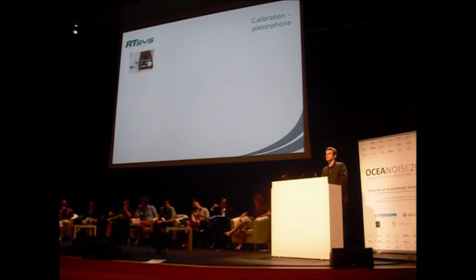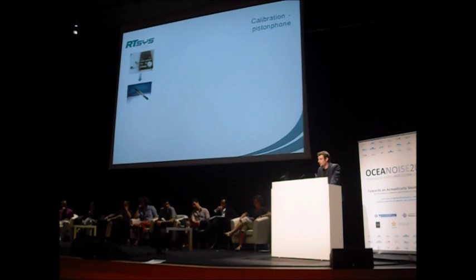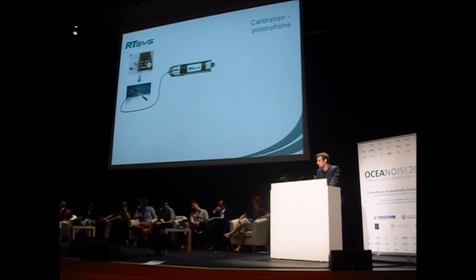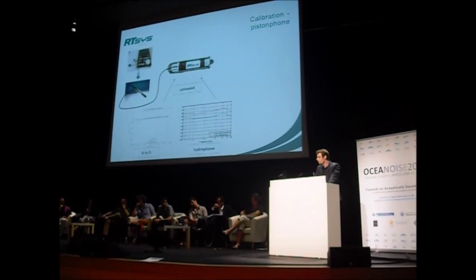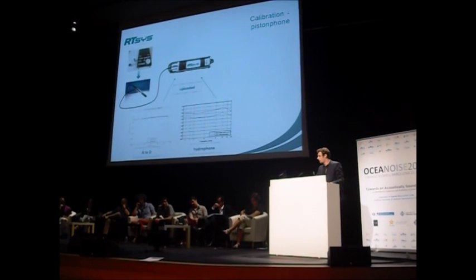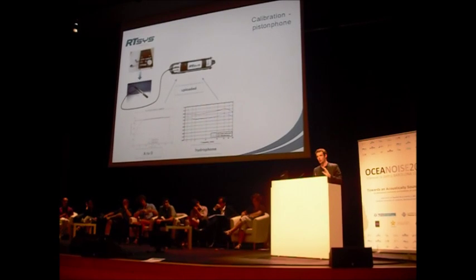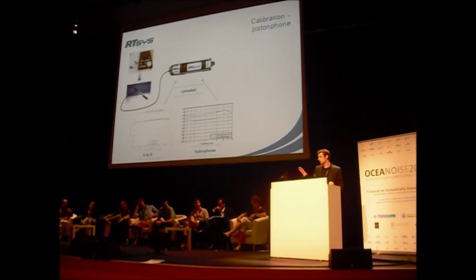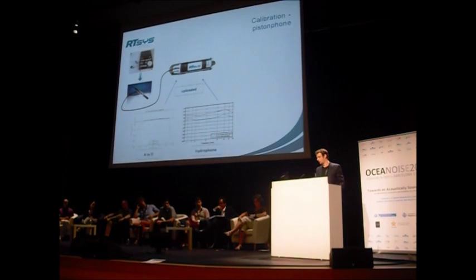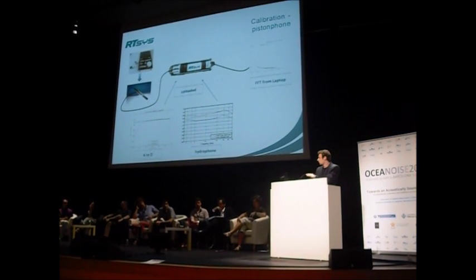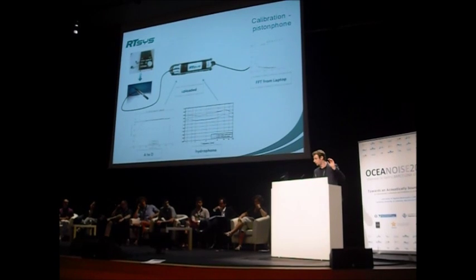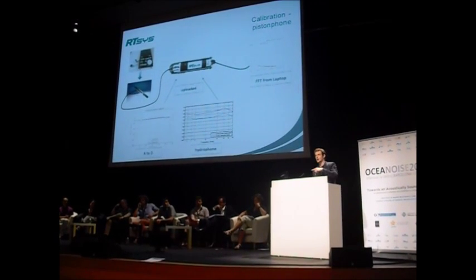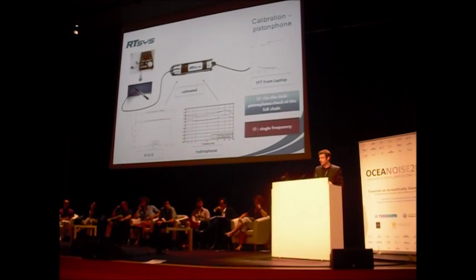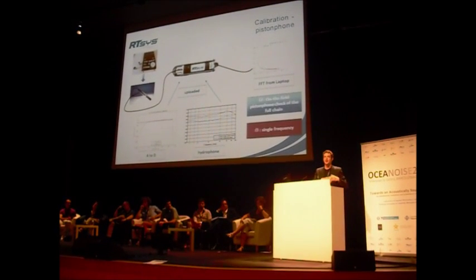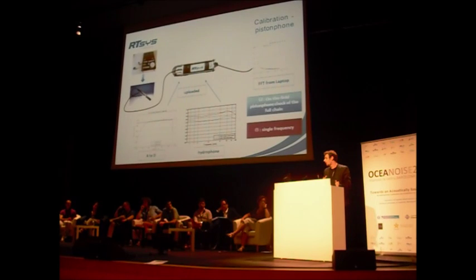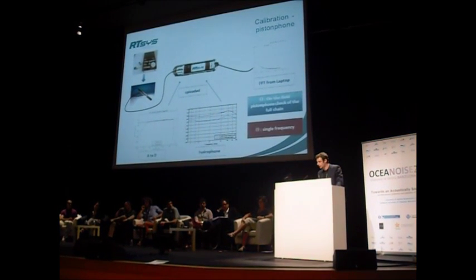Another measurement is piston phone calibration. So you have your piston phone connected to your hydrophone, then to your recording system. And what you can do with our system, which is interesting, is upload both the calibration of the A to D converter and the calibration of the hydrophone, and visualize in real time from a laptop the peak of 250 Hz of your piston phone and check if the whole chain is fully calibrated. So the interesting thing is you can make an order of magnitude check of the whole chain. The drawback is that it is still a single frequency check.